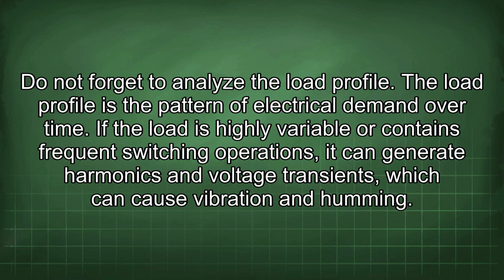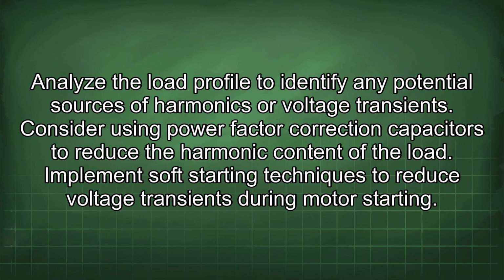Do not forget to analyze the load profile. The load profile is the pattern of electrical demand over time. If the load is highly variable or contains frequent switching operations, it can generate harmonics and voltage transients, which can cause vibration and humming. Analyze the load profile to identify any potential sources of harmonics or voltage transients. Consider using power factor correction capacitors to reduce the harmonic content of the load. Implement soft starting techniques to reduce voltage transients during motor starting.